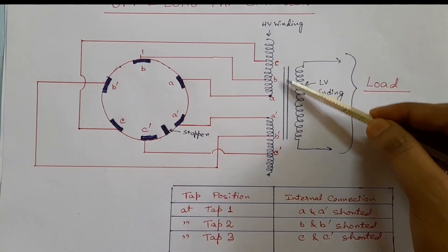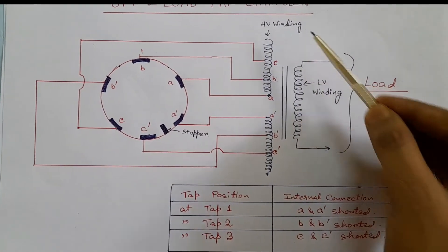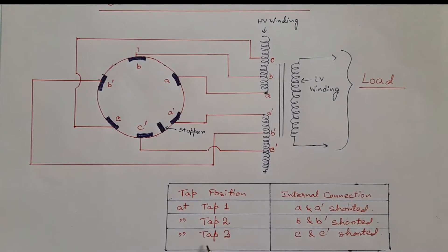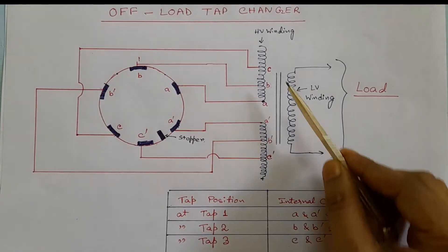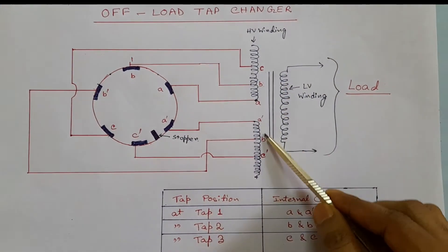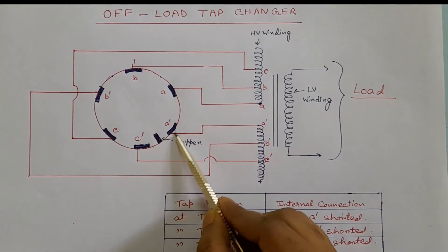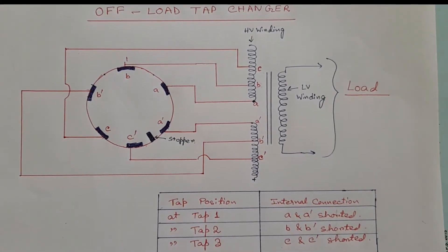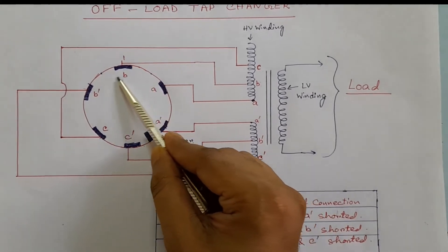Notice that there are six taps in the high voltage winding, but we have only three selectable tap positions in this off-load tap changer. Also notice that these six taps are connected with six studs in the off-load tap changer, and these studs are not connected with each other.